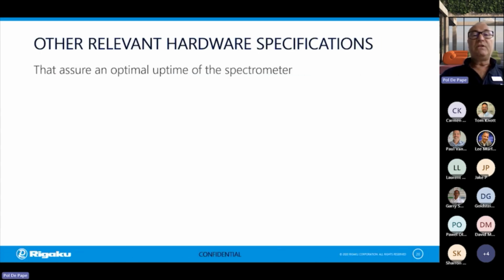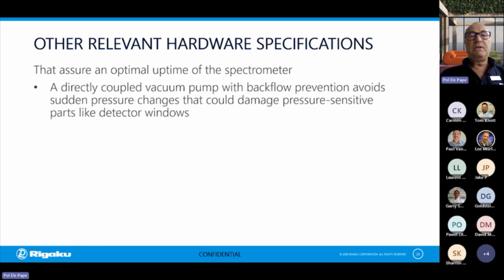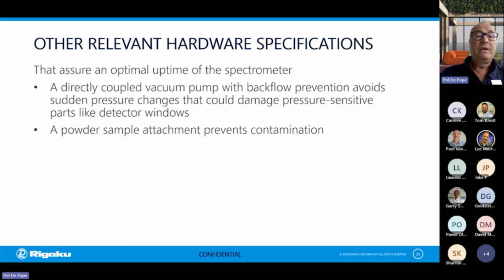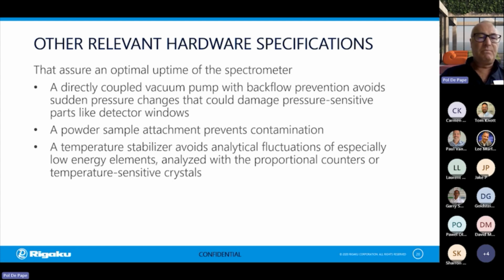Some other relevant hardware specifications which assure an optimal uptime of the spectrometer. So we have a directly coupled vacuum pump with a backflow prevention. So if this backflow prevention wouldn't be there, it could, for example, happen that all of a sudden you get some pressure change, which would make the window of the detector break, for example. We also have a powder sample attachment. So in case some loose powder floats around in the spectrometer, we have a filter that takes those particles. We have a temperature stabilizer that avoids analytical fluctuations, especially for the light elements.